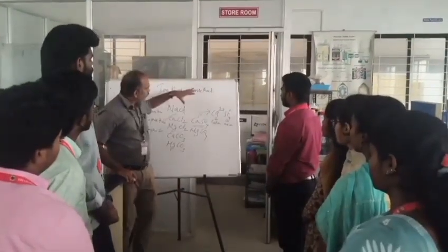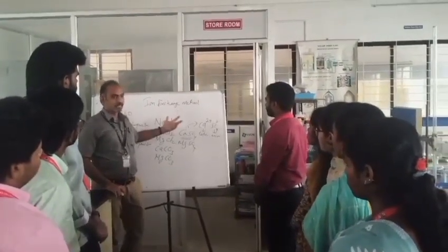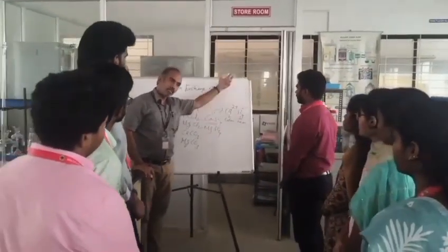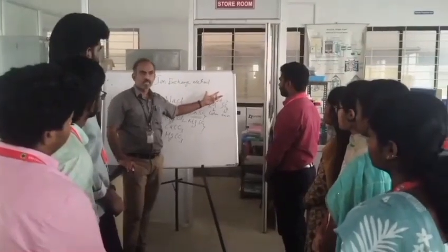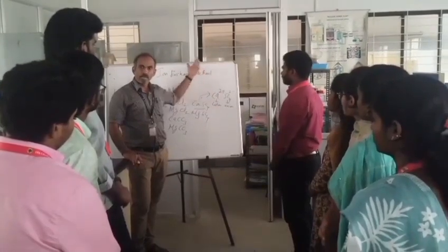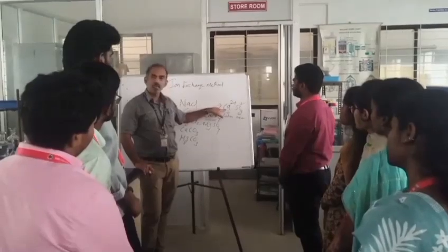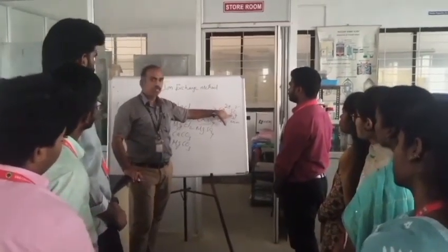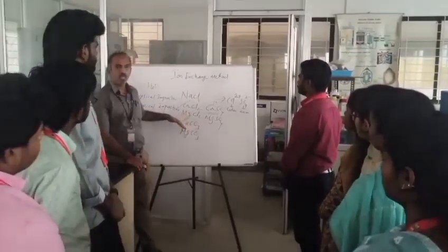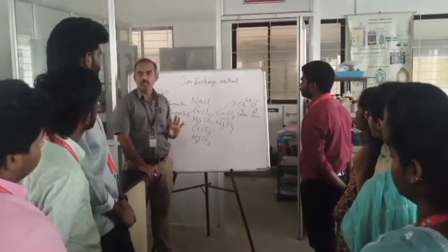Okay. So in this method, ion exchange means they exchange the ions. One resin removes the calcium, and another resin removes the sulfate ions, so we use two columns: a cation resin and an anion resin. The cation resin removes calcium and the anion resin removes the sulfate. With this kind of approach, impure water is converted into pure water.